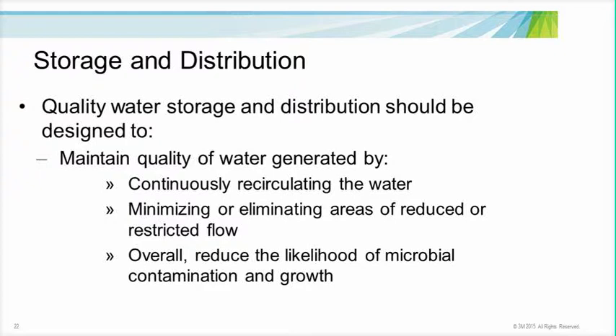Once the quality water is generated, it is stored and ready for distribution. The key in storage and distribution is to maintain the original quality of the generated water throughout the entire system. This is accomplished by proper system design and operation, by continuously recirculating the water, minimizing or eliminating areas of reduced or restricted flow, and minimizing the likelihood of microbial contamination and growth through high flow rates and proper maintenance.